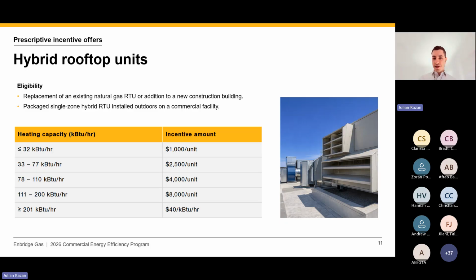You can take advantage of this incentive if you have a gas-fired unit that you're replacing with a hybrid unit. The table shows that based on the capacity of the unit, as it increases, the incentive also increases. The heating capacity on the left is based on the heat pump heating capacity, not the gas side. As that increases, your incentive increases, and if you go over 200 kBTU, it goes to $40 per kBTU. I think it's a really lucrative incentive, and typically it covers the cost difference between a regular gas-fired unit and this premium option.